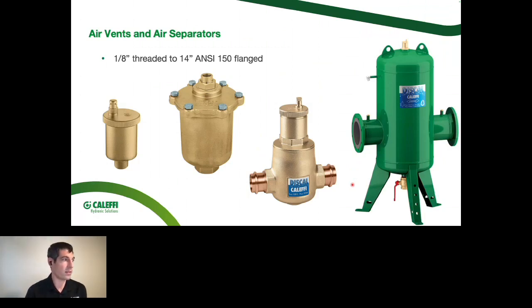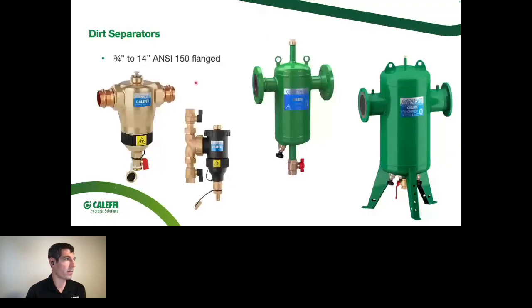Okay, I'm going to just go through a couple slides at the end here to show the different sizes of these devices. So air vents and air separators can go from 1/8 inch to 12 inch in Canada for CRN listings if that's required, and then 14 inch for the bigger separators down in the States. Same thing here, 3/4 to 12 inch for the Canadian devices. In the bigger dirt separators, the flange versions, there's still a dry well magnet down here, so you don't have to get your hands dirty with the magnetite or anything like that. You just pull that out, blow this down into a bucket, and you don't have to touch or disassemble the components at all. In the biggest versions, it's actually 3 different stacks of magnets that go up into the vessel to grab the magnetite with higher flow rates.